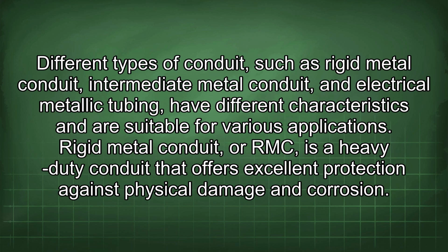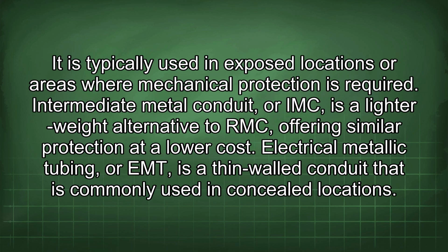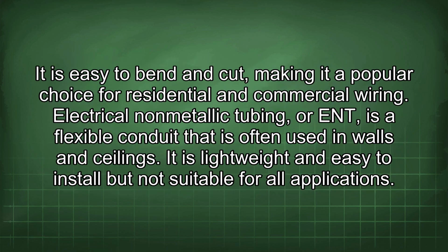Rigid metal conduit, or RMC, is a heavy-duty conduit that offers excellent protection against physical damage and corrosion. It is typically used in exposed locations or areas where mechanical protection is required. Intermediate metal conduit, or IMC, is a lighter weight alternative to RMC, offering similar protection at a lower cost. Electrical metallic tubing, or EMT, is a thin-walled conduit that is commonly used in concealed locations. It is easy to bend and cut, making it a popular choice for residential and commercial wiring. Electrical non-metallic tubing, or ENT, is a flexible conduit that is often used in walls and ceilings. It is lightweight and easy to install, but not suitable for all applications.